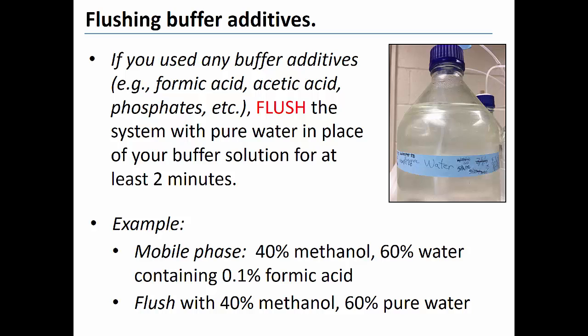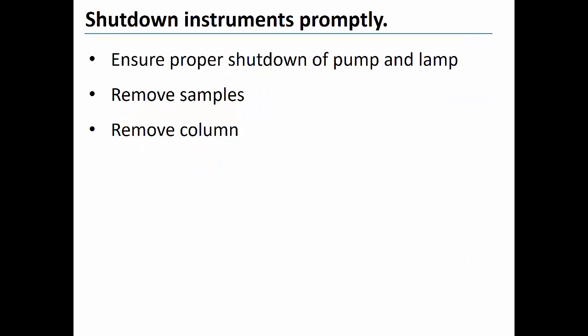Additional essential shutdown steps include turning off the pump, turning off the lamp, removing sample vials from the auto sampler tray, and removing your column.